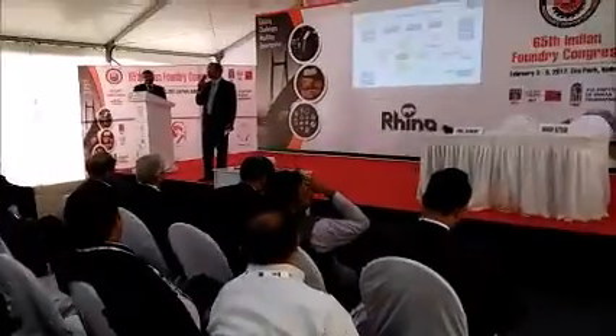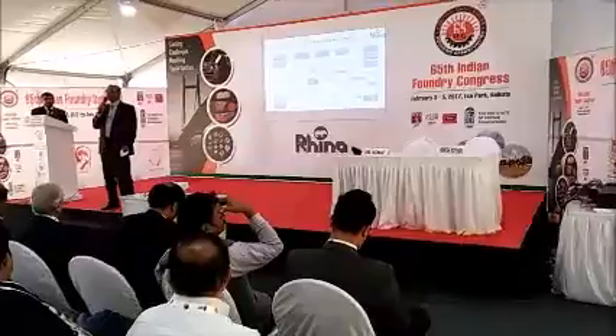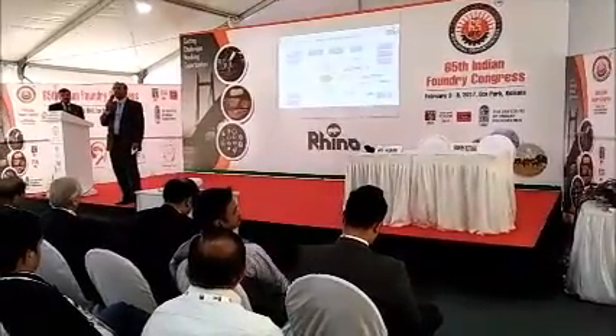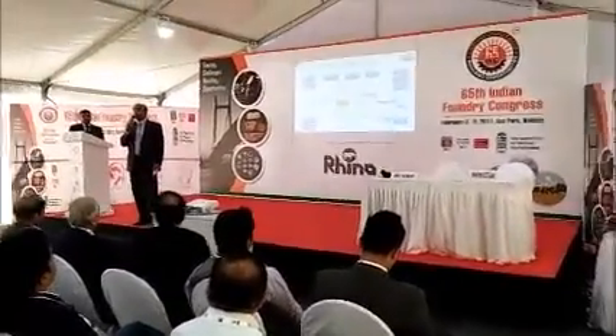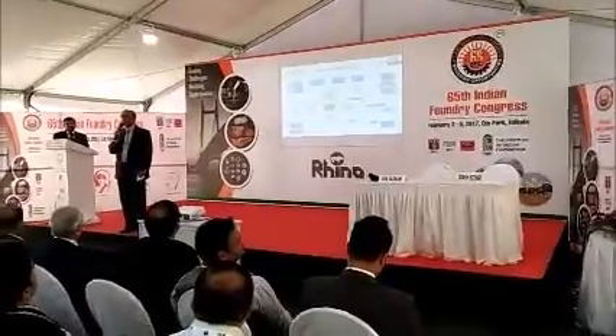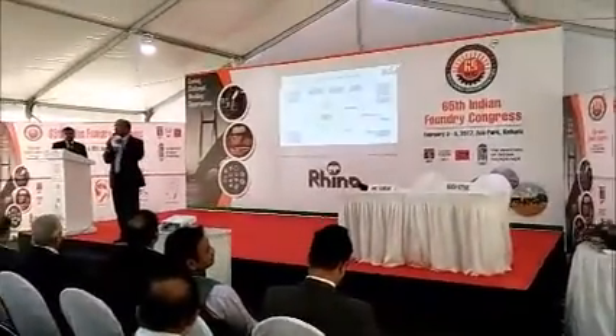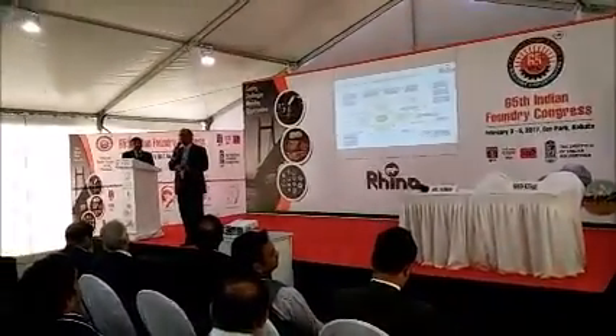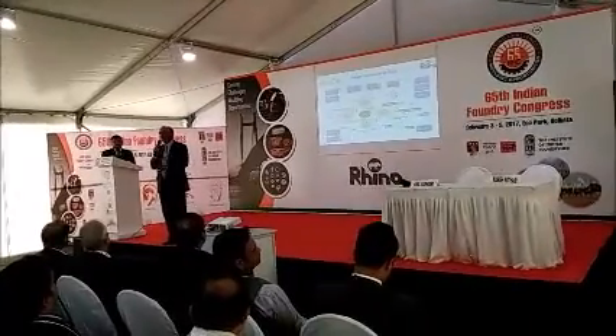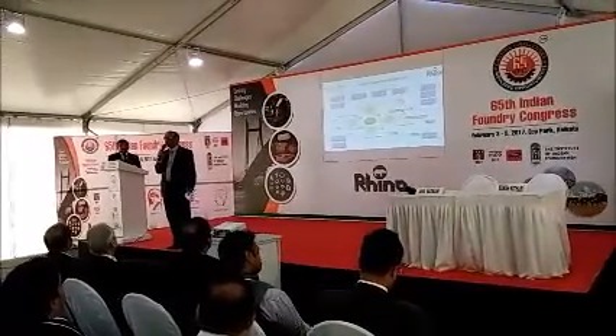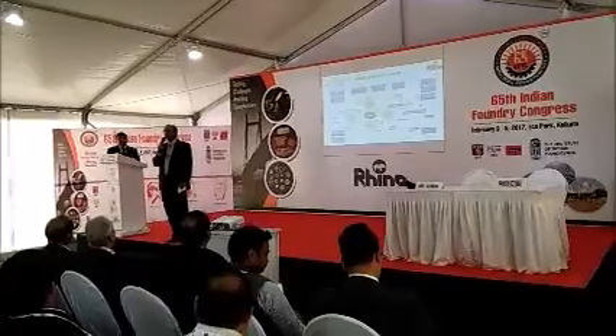For example, sand mixer machine, I have seen at some places the current drawn required is 15 ampere, but in some cases it draws 25-30 ampere. So there are chances that the motor will get burned. So you can get an alert from that energy meter that instead of 15 ampere, now it is drawing 20 ampere. So you can get SMS on your mobile that current drawn is more. Look at whether the shaft is bent or the bearing has gone, or sand instead of 300 kg he has put 400 kg. That you can always analyze correctly.